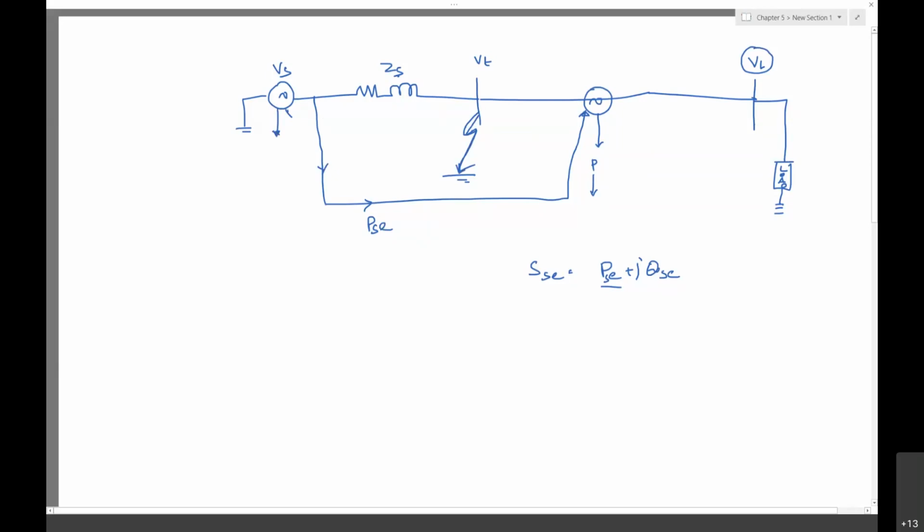Once you say that this particular source is driving this particular fault current, we can't load more than that, because the source itself has reached its maximum short circuit capacity also. So we can't draw the power for this compensator from the same source. For that reason, we can have a standby source.